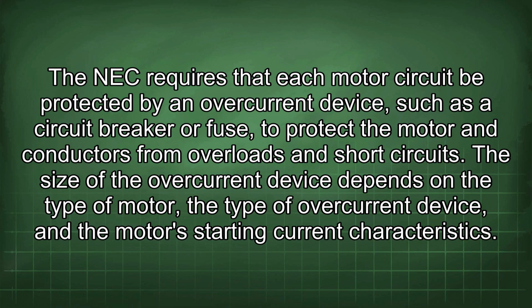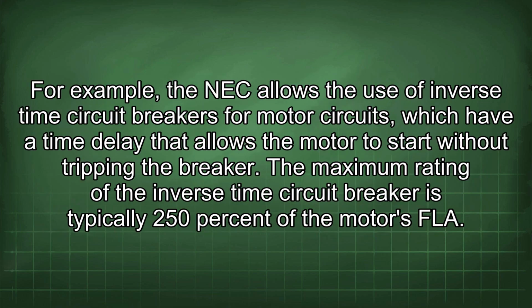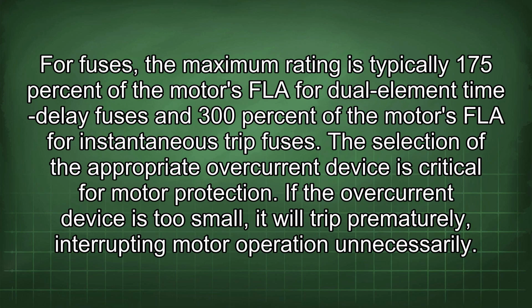The size of the overcurrent device depends on the type of motor, the type of overcurrent device, and the motor's starting current characteristics. For example, the NEC allows the use of inverse time circuit breakers for motor circuits, which have a time delay that allows the motor to start without tripping the breaker. The maximum rating of the inverse time circuit breaker is typically 250% of the motor's FLA. For fuses, the maximum rating is typically 175% of the motor's FLA for dual-element time delay fuses and 300% of the motor's FLA for instantaneous trip fuses.